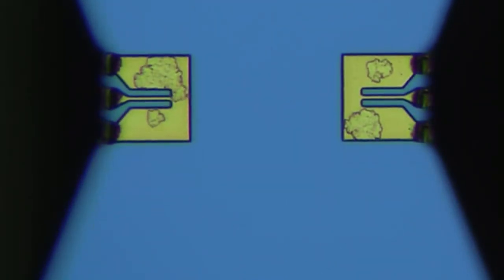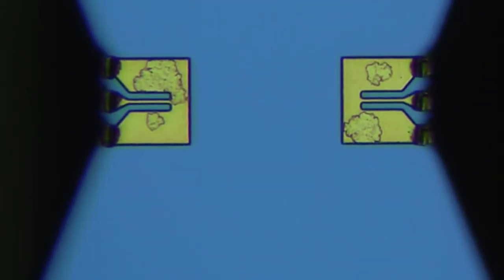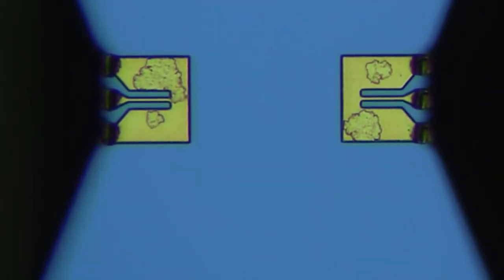The short has the same separation distance as the open. Align the marks. Check the over travel and then move to the short standard. WinCal then makes short measurement and stores the data.